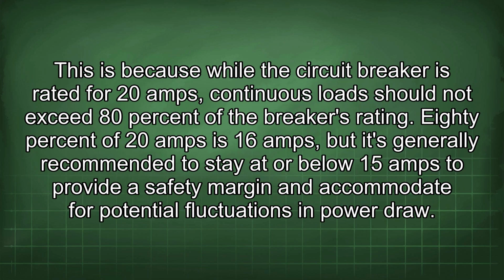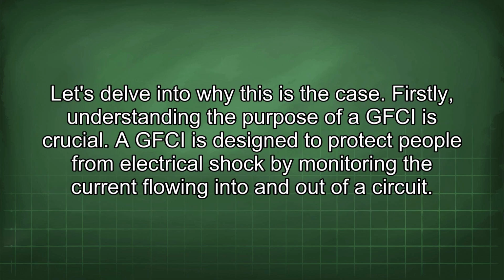This is because while the circuit breaker is rated for 20 amps, continuous load should not exceed 80% of the breaker's rating. 80% of 20 amps is 16 amps, but it's generally recommended to stay at or below 15 amps to provide a safety margin and accommodate for potential fluctuations in power draw. Let's delve into why this is the case.